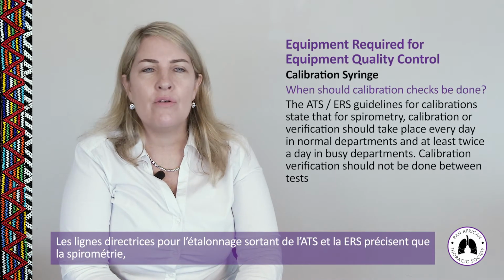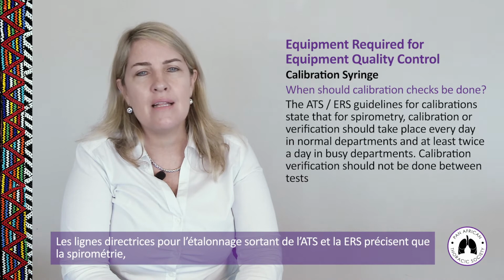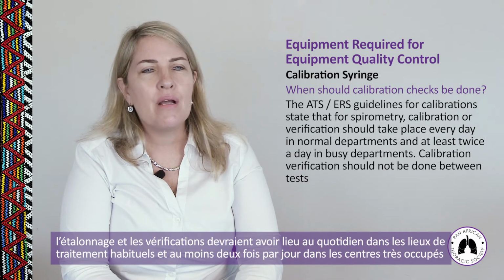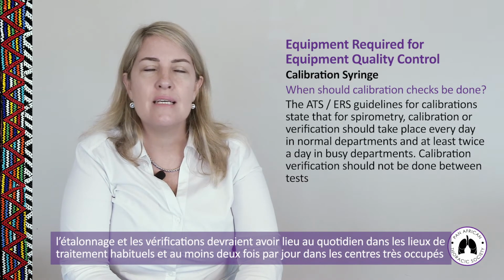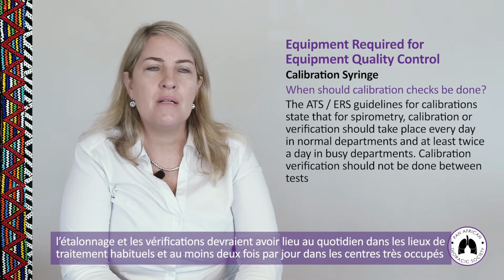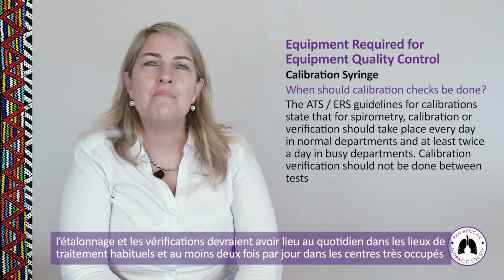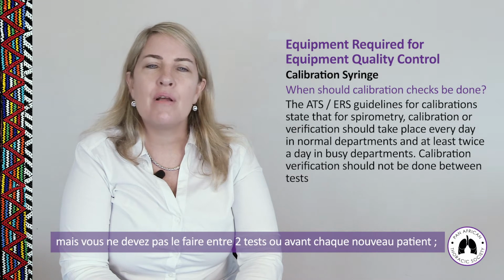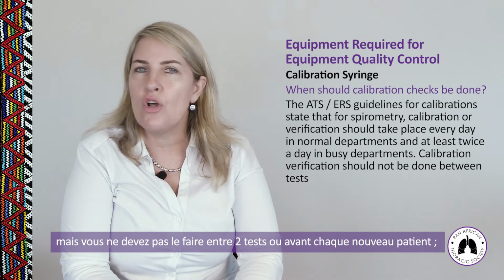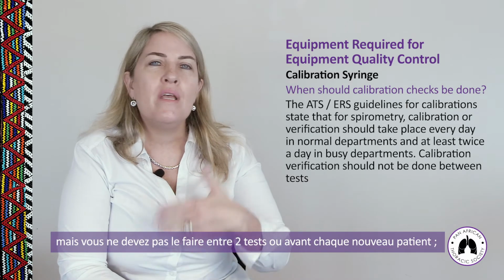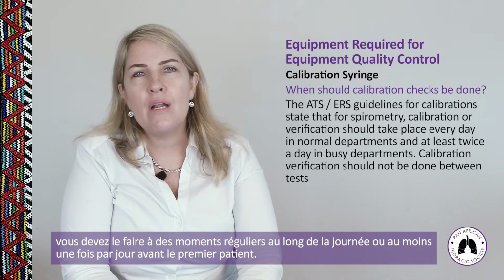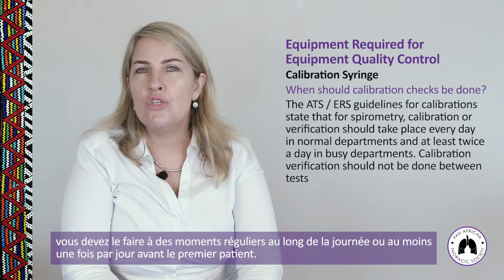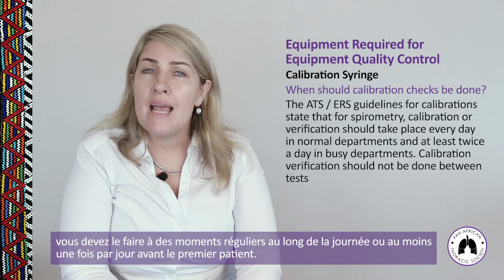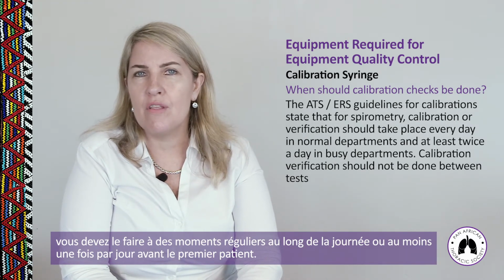So the ATS ERS guidelines for calibration state that for spirometry, calibration or verification should take place every day in normal departments and at least twice a day in busy departments. So calibration verification should not be done necessarily between tests. You don't have to do this before each new patient. You need to do it at regular points during the day or at least daily before the first patient of the day.